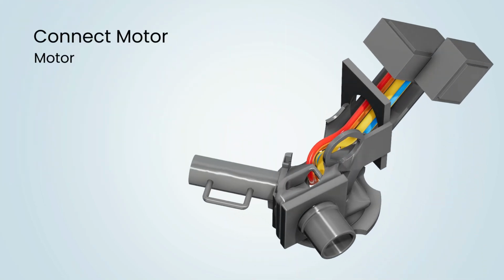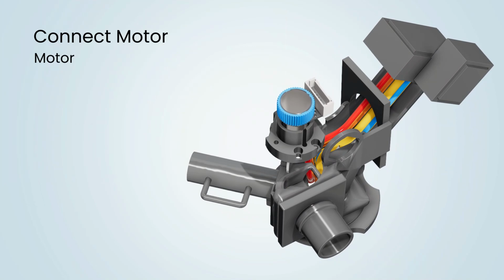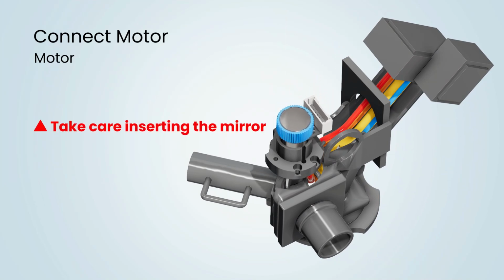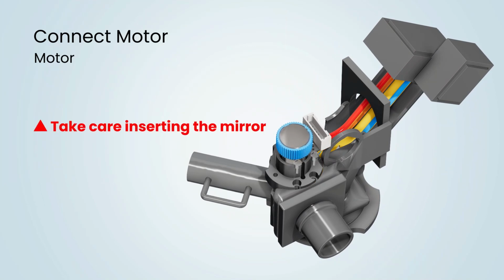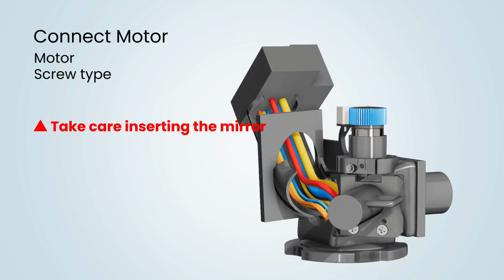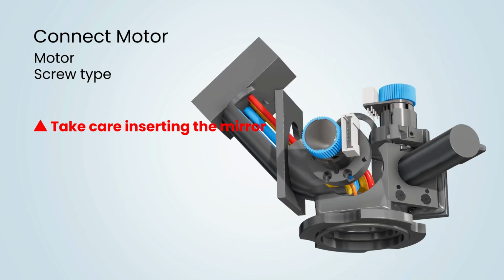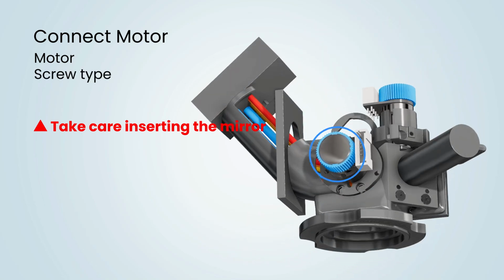Next, connect the motor to the assembly. Take care to not damage the mirrors as it is inserted. Secure the motor using 2 screws and Loctite 242. Connect the second motor to the assembly. Take care to not damage the mirrors as it is inserted. Secure the motor using 2 screws and Loctite 242.